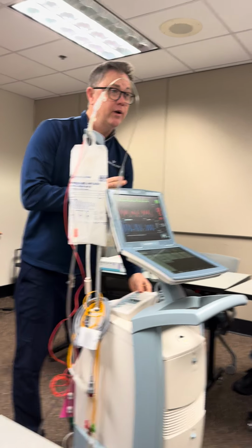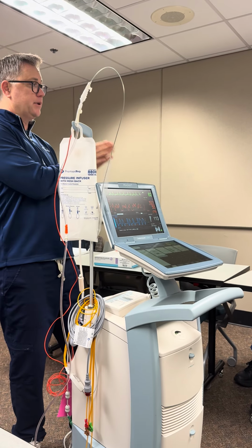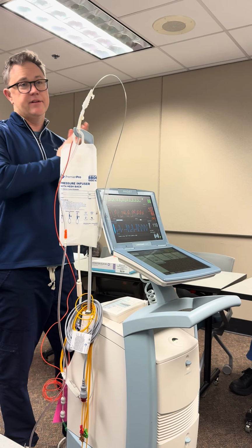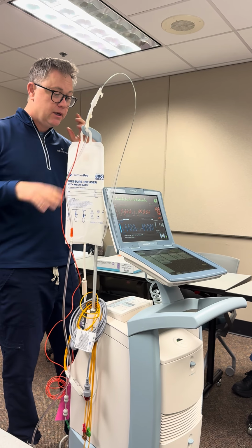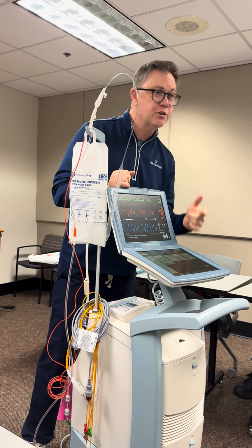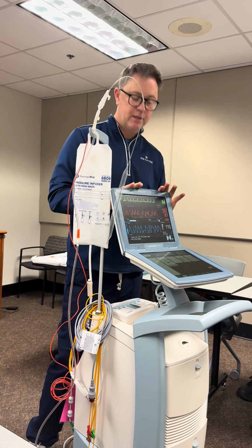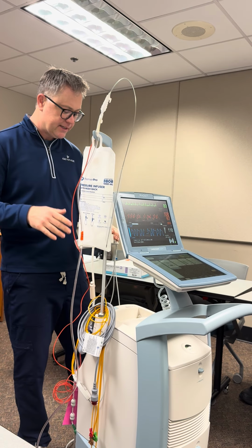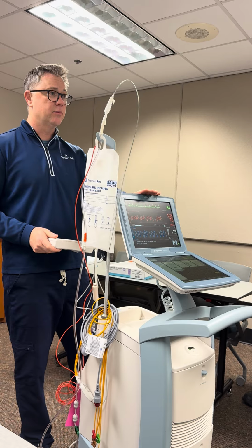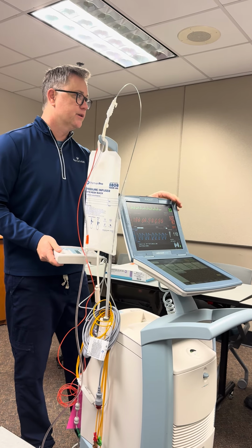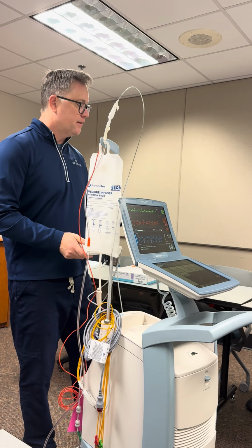Now, because those R waves aren't regular, we're not able to base our timing on it. As soon as it sees an R wave, it's just going to rapidly deflate the balloon. So you don't need to do anything. You don't need to put it into pressure trigger or 1 to 2 or anything like that. Balloon pump's going to recognize that. Same with couplets, VTAC, PVCs, all of those things. The balloon pump will recognize it. Obviously, you want to treat the rhythm, but it will continue to augment those rhythms.